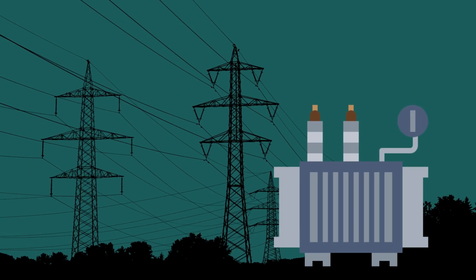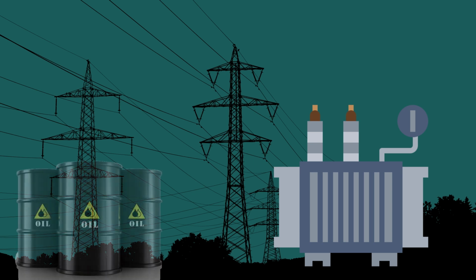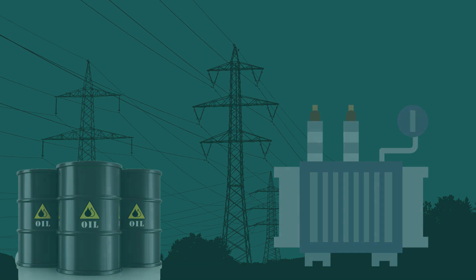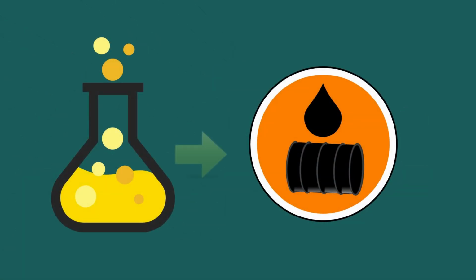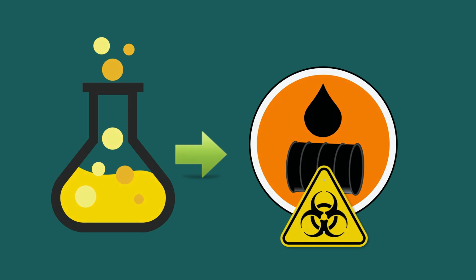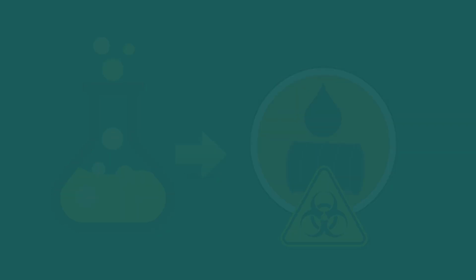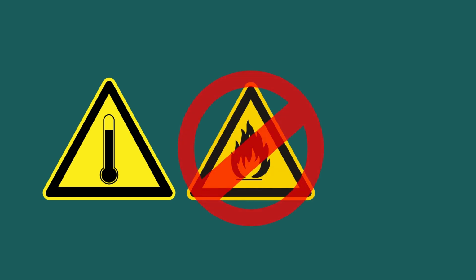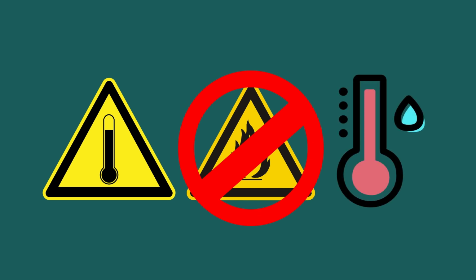Synthetic silicone transformer oils appeared first in the transformer maintenance market in the 70s of the last century as one of the alternatives to polychlorinated biphenyls, which were classified as carcinogenic pollutants. At that time the expansion of silicone transformer oils was facilitated by a high flash point and a tendency to self-extinguish, which distinguished them in terms of fire safety, as well as resistance to oxidation and thermal degradation.